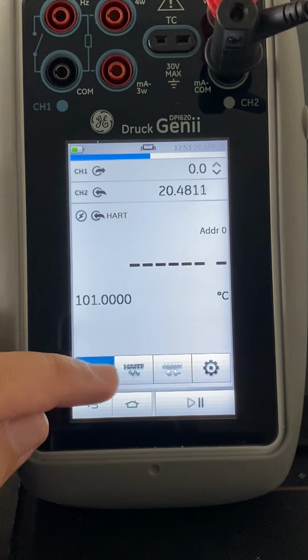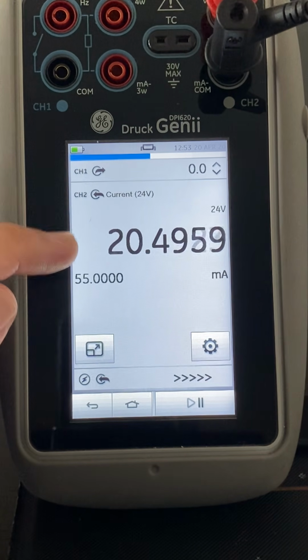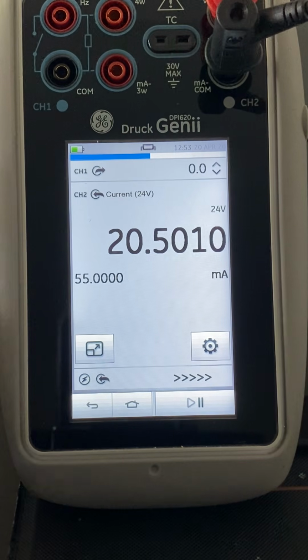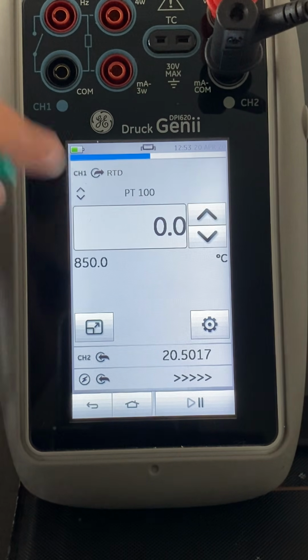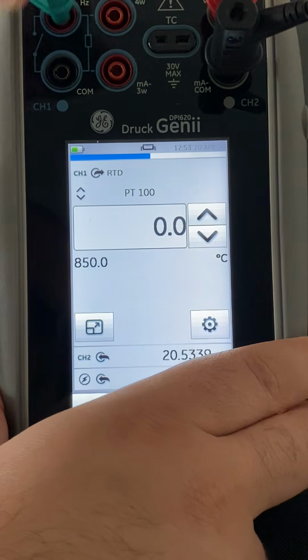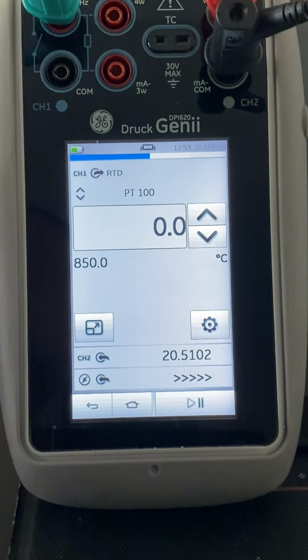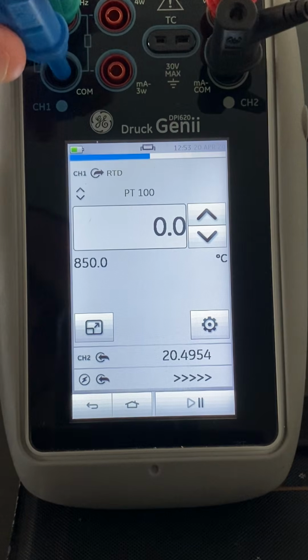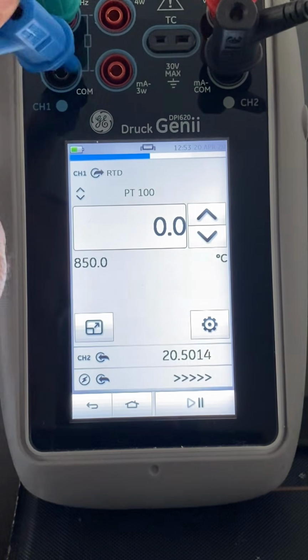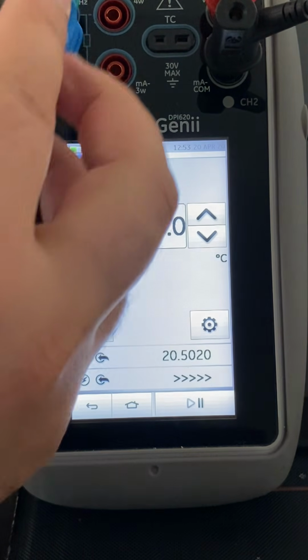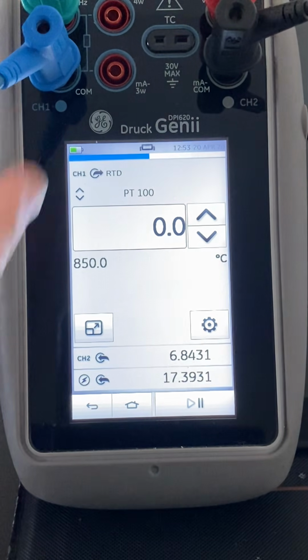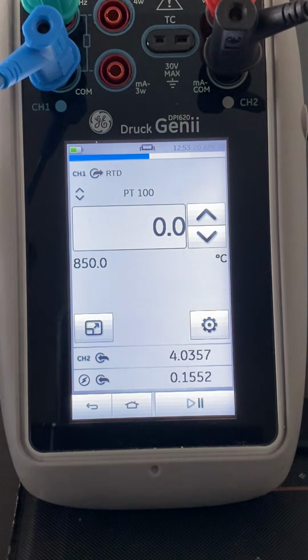So the transmitter power is up and it's giving me overrange because the input is not connected. The input I already configured to the RTD, so I can communicate without connecting the input, that's fine. But the reason I'm connecting the input is to show you how I can utilize the calibrator with the communicator together.